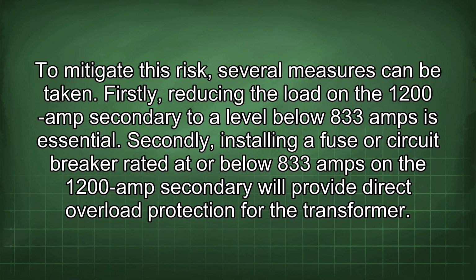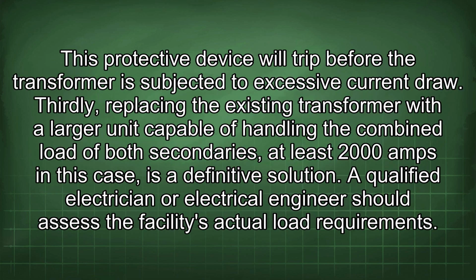To mitigate this risk, several measures can be taken. Firstly, reducing the load on the 1200 amp secondary to a level below 833 amps is essential. Secondly, installing a fuse or circuit breaker rated at or below 833 amps on the 1200 amp secondary will provide direct overload protection for the transformer. This protective device will trip before the transformer is subjected to excessive current draw. Thirdly, replacing the existing transformer with a larger unit capable of handling the combined load of both secondaries, at least 2000 amps in this case, is a definitive solution. A qualified electrician or electrical engineer should assess the facility's actual load requirements.